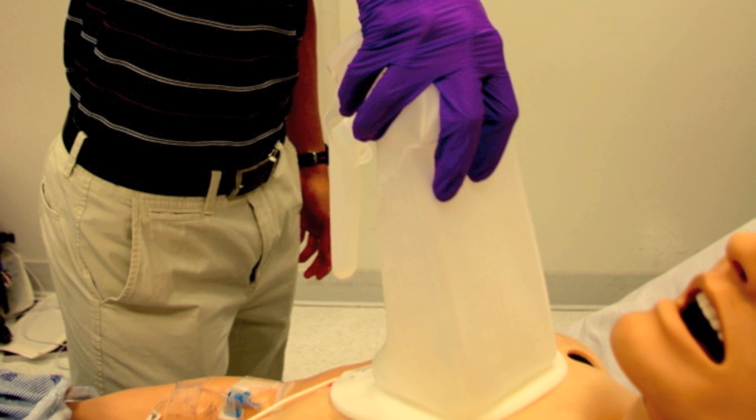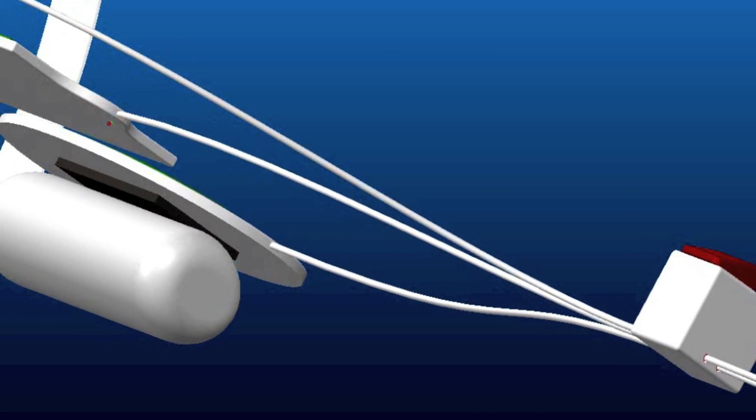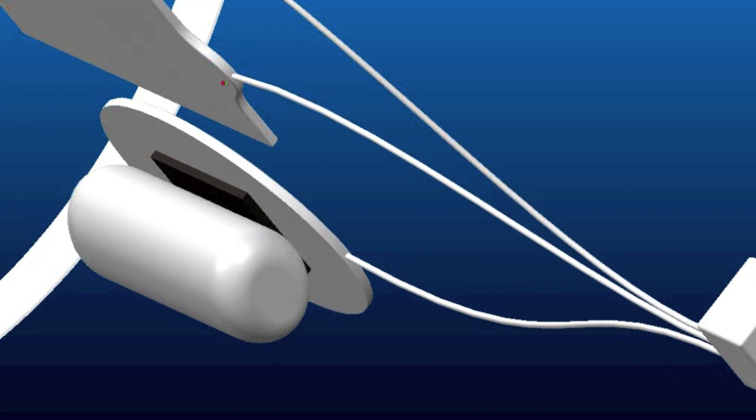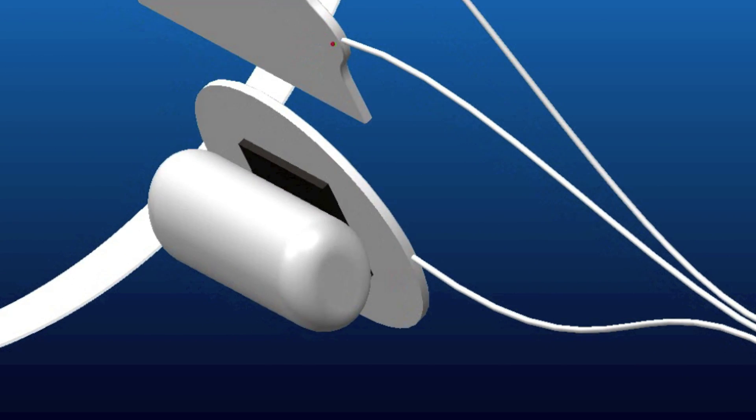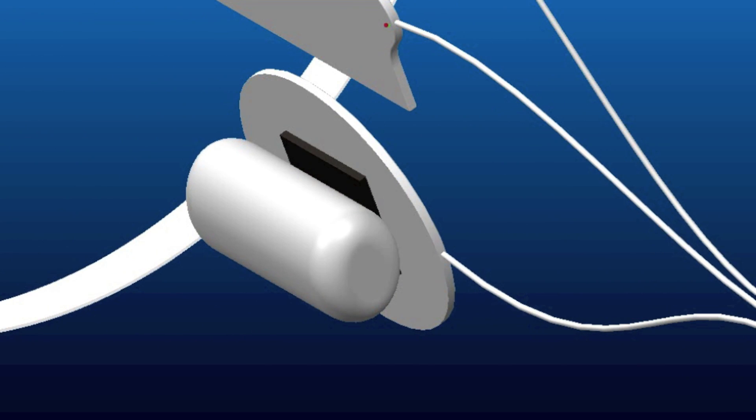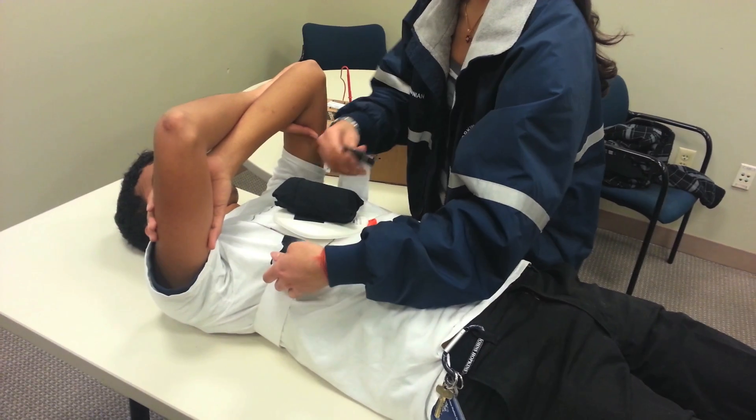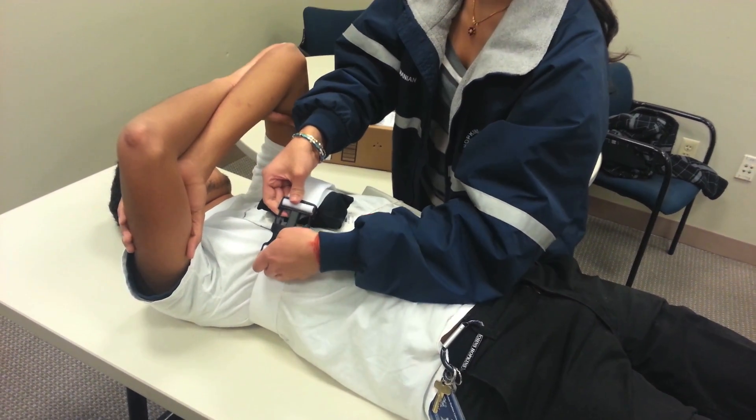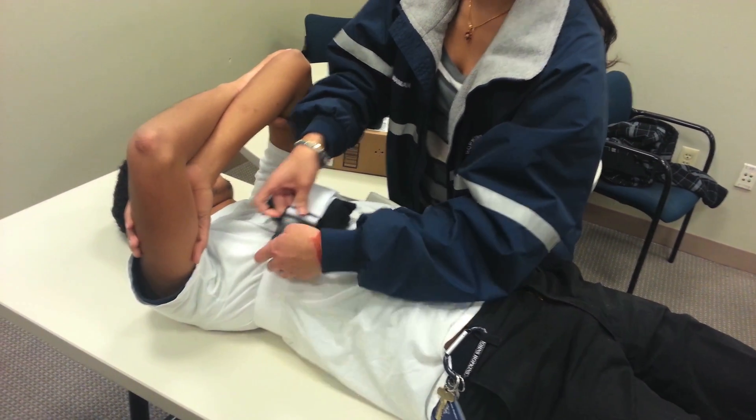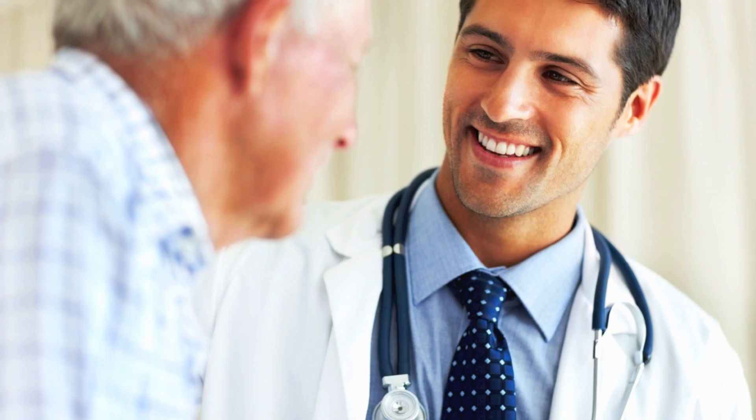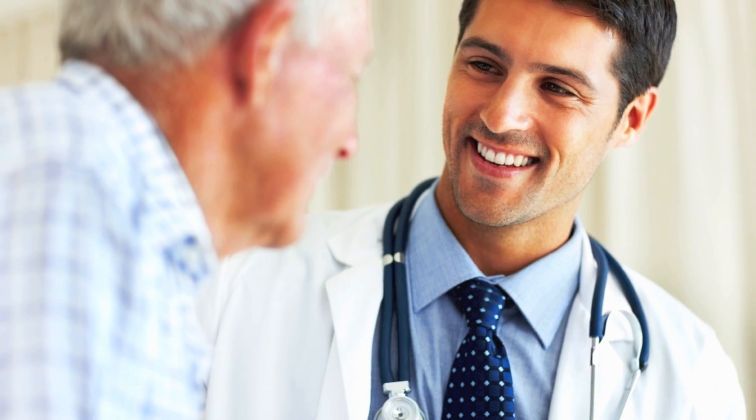The Presto Patch uses a simple strap design around the chest with a fulcrum to exert pressure directly over the front patch, so the doctor doesn't have to be touching the patient during the shock.